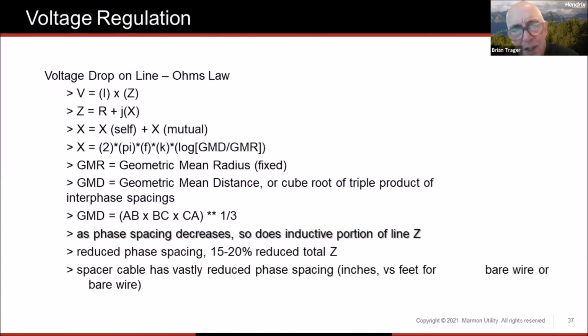Another application that people really don't realize, and I won't dwell on this because this is not a mathematics tutorial here, but talk about voltage drop. How do we benefit when we go from bare wire to spacer cable? Well, what we're doing is reducing the space between our individual phase conductors. We're going from 6 or 8 or 10 feet down to 12 inches between those phase conductors. As we reduce the phase conductor distance, we reduce the GMD, the geometric mean distance, and therefore we're reducing or eliminating, canceling out the mutual inductance portion of the total impedance.